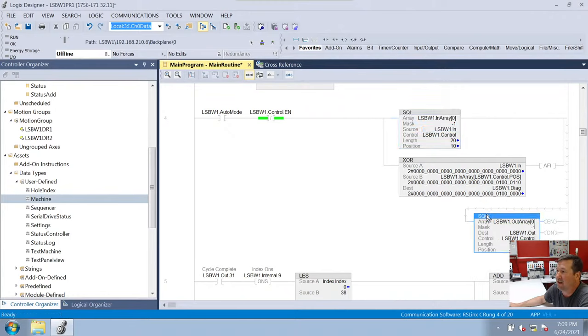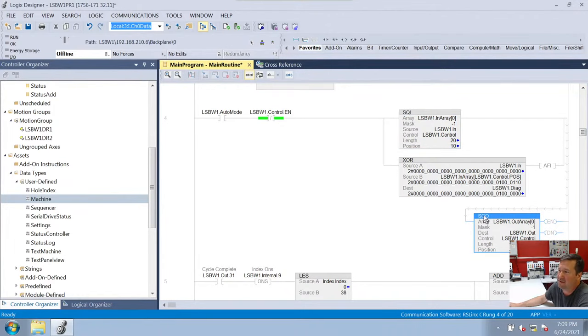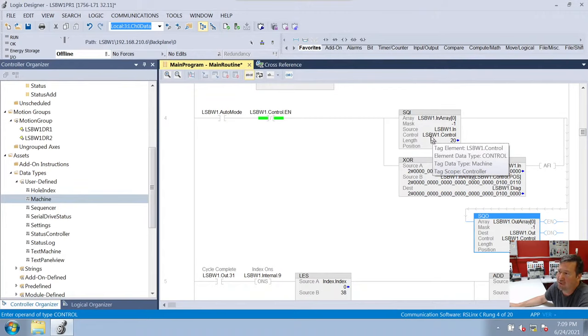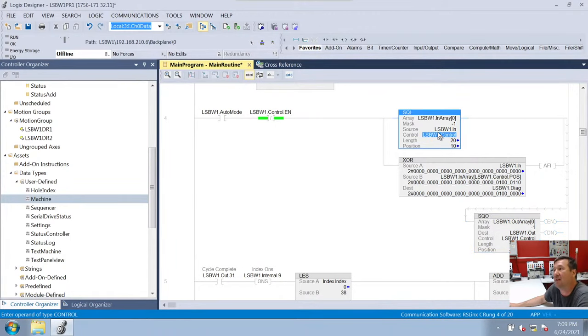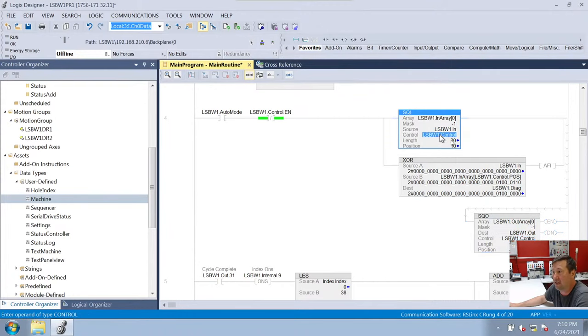The SQI sequencer input and SQO sequencer output are locked together by a shared control. The control of this one is LSBW1.control, and LSBW1 was the name of this machine. That control is the exact same for both, so as one of them advances, the other one will advance too — that's what ties them together.